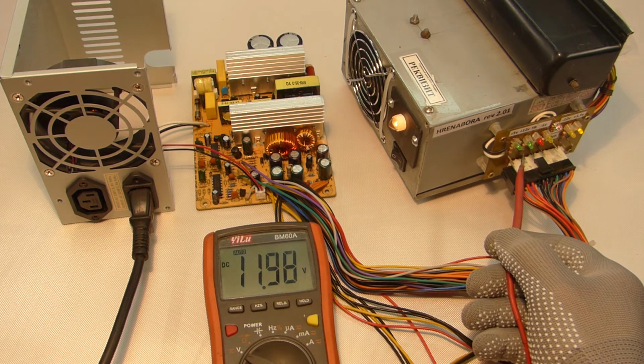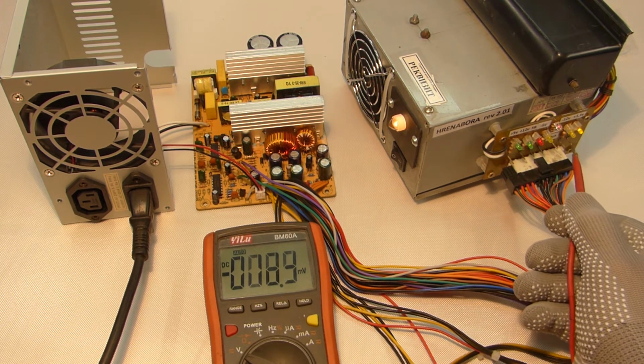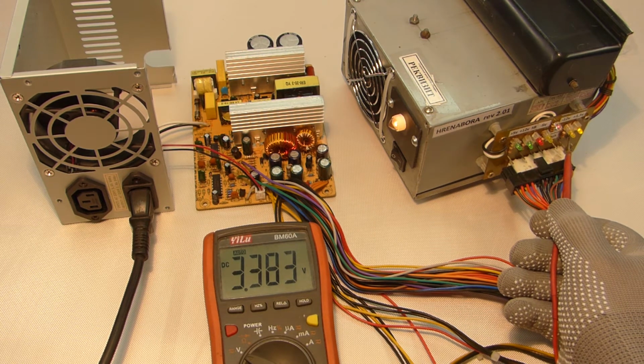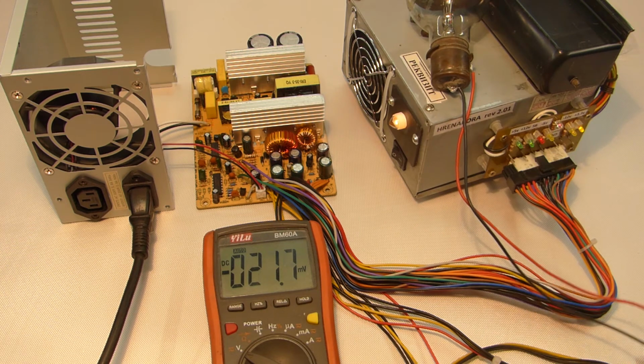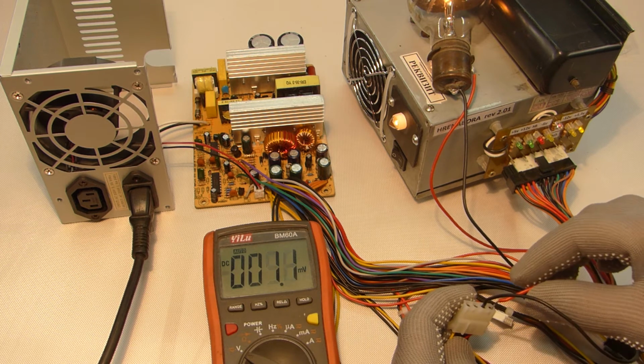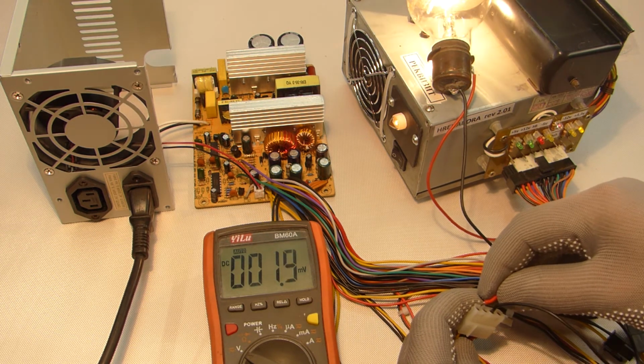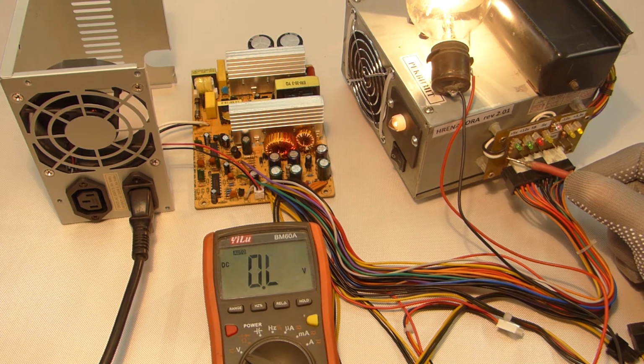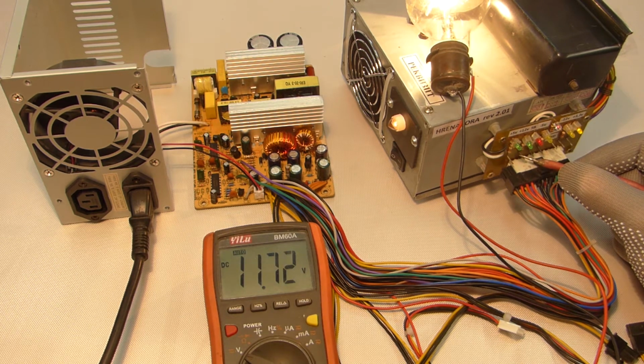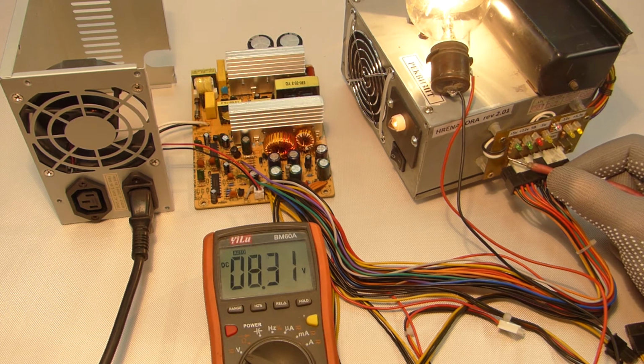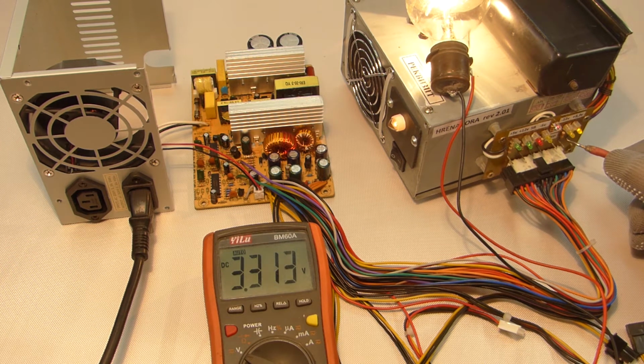I'll check the voltage for every rail. 5V rail, 5V. 12V rail, 11.97V. 3.3V rail, 3.38V. Now let's add some extra load, about 100W. In 5V rail, the lamp is glowing, protection doesn't react. In 12V rail, the lamp is shining, protection doesn't cut the power either. Check the readings of the rails under load: 12V rail dips down to 11.72V, 5V rail to 4.98V, 3V rail to 3.31V. All voltage readings under load are within the permitted range.